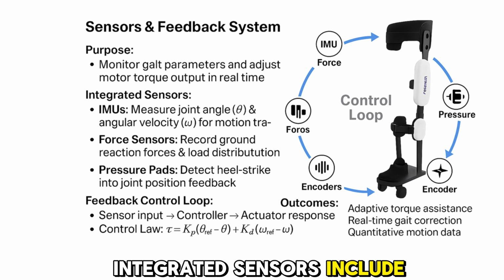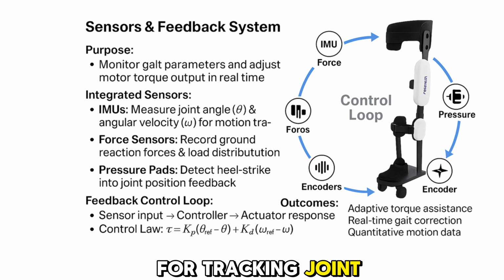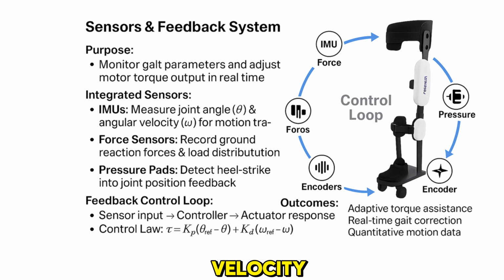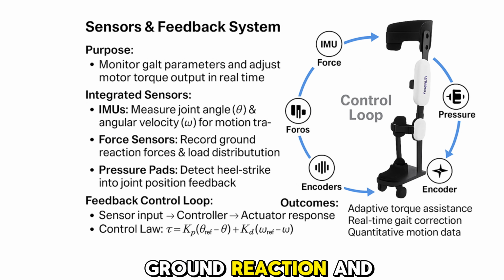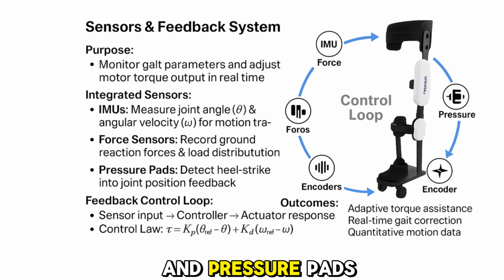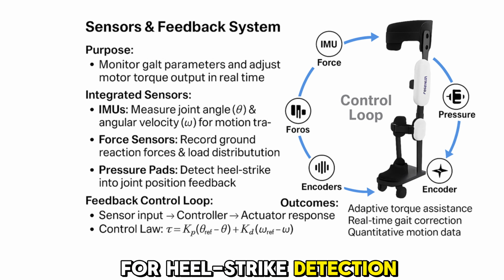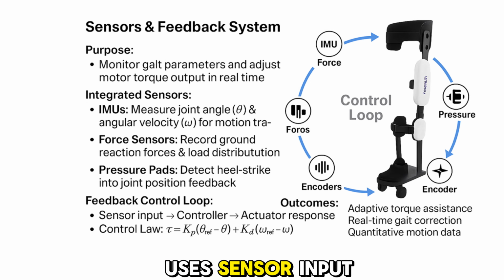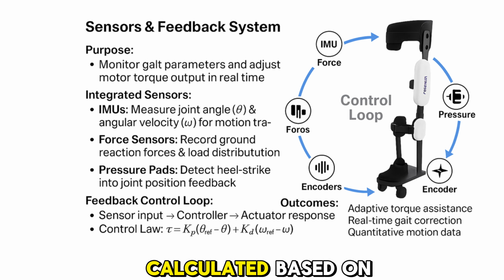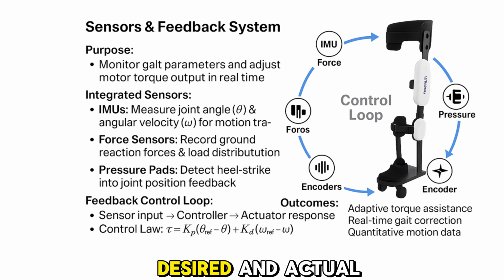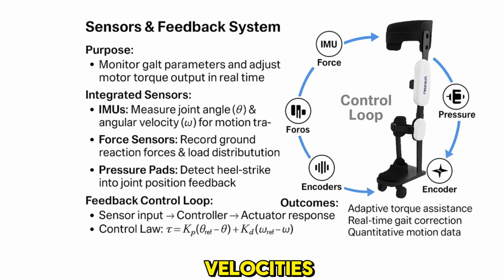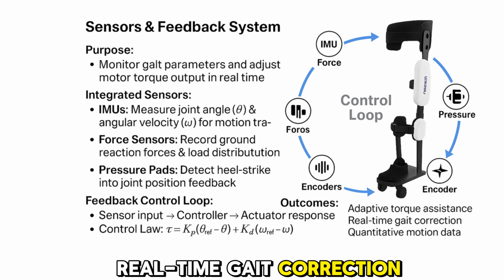Integrated sensors include inertial measurement units for tracking joint angles and angular velocity, force sensors for ground reaction and load distribution, and pressure pads for heel strike detection. The feedback loop uses sensor input to adjust actuator response. Torque output is calculated based on the difference between desired and actual joint angles and velocities. This enables adaptive assistance, real-time gait correction, and quantitative motion tracking.